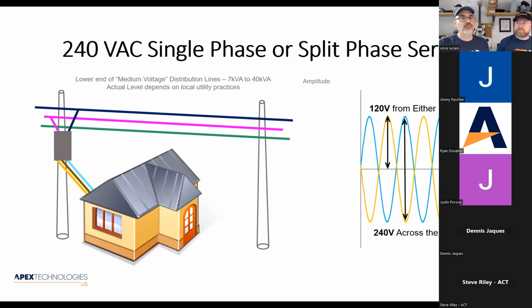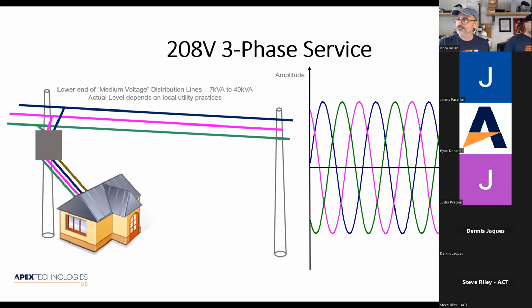So why do we need 240 volts in a house? Well, your electric oven needs to pull a lot of power. One way you could do it, you could run your oven off 120 volts, but you'd really need thick wire to be able to supply the current, because remember, power is voltage times current. So if the voltage is low, the current has to go high in order to come up with that same number. But they found it's much easier, much more cost effective, that if we power our high power devices like ovens, electric dryers, and HVAC systems off of 240 volts, the wire size can be much smaller and it's much more economical.